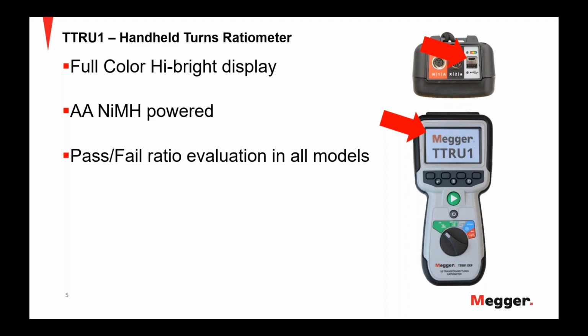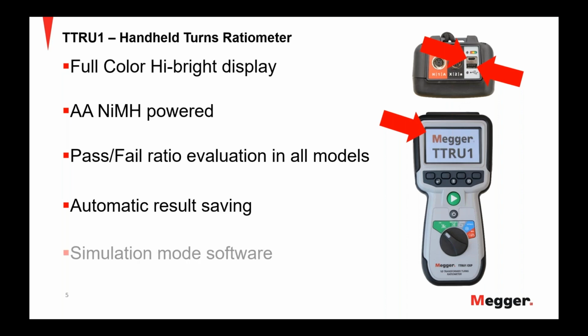One thing that we include now in all of the models is the ability to enter the nameplate voltages of the transformer and then provide the pass-fail ratio evaluation directly on screen. And when you run tests, they are automatically saved. And we also have included on the top, as you'll see there, another USB connection, USB-A, and this will be used for a USB drive or for the optional 2-inch printer for you to keep a record of those results after they're saved on the device.